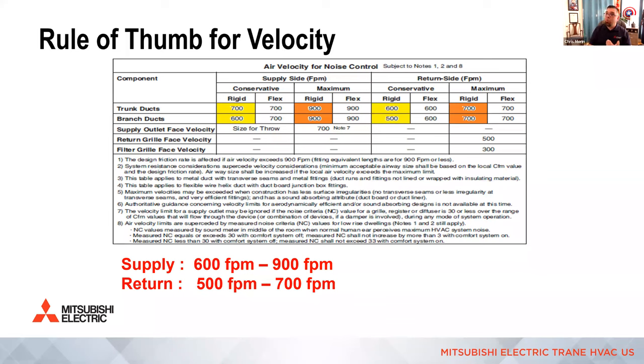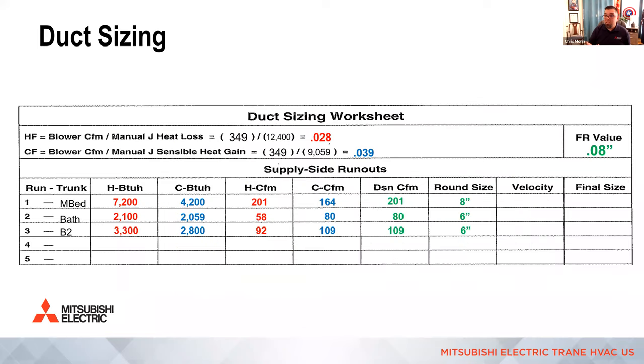So it's really important when you select registers, if you're not familiar, definitely get a copy of Manual T. It's duct layout, and it'll help you decide on throw. So what you'll find is a lot of people, instead of, let's say, putting a supply register by a window in order to sweep the window, because you have to throw so far, they might put a central register that blows four ways, and you only have to blow half the distance, right?